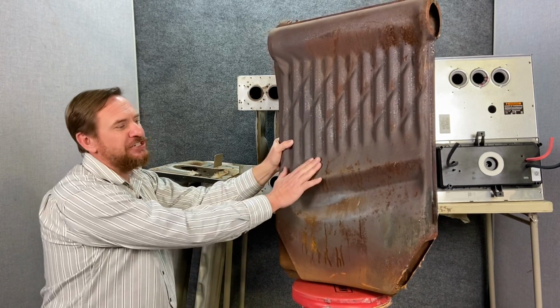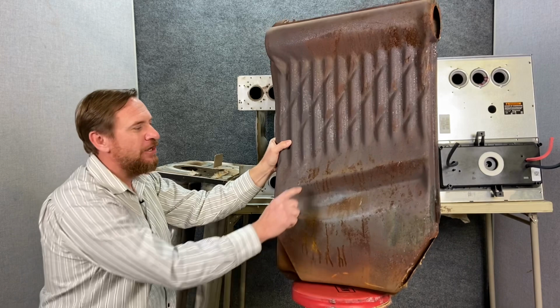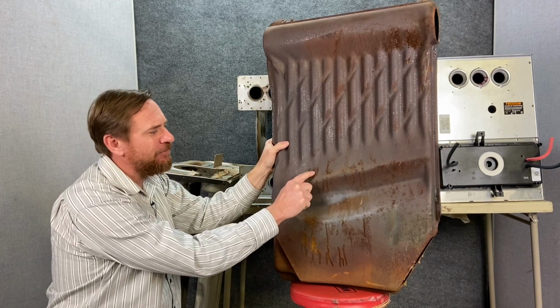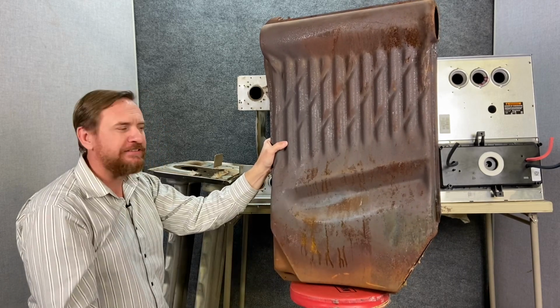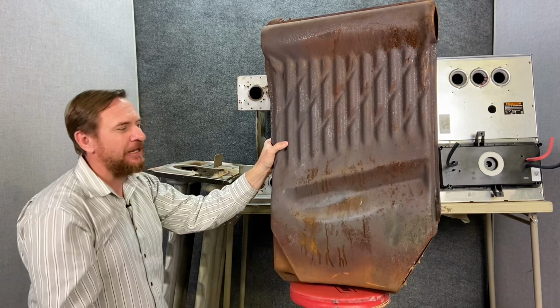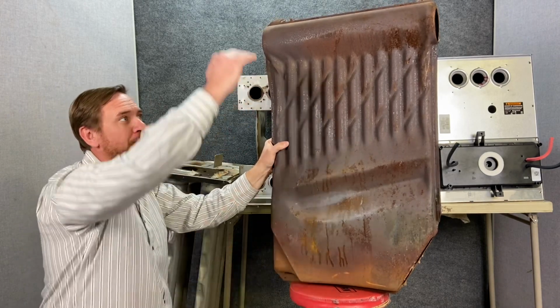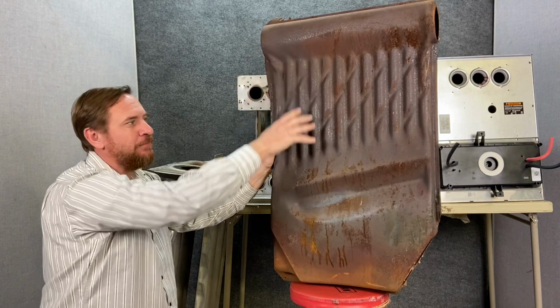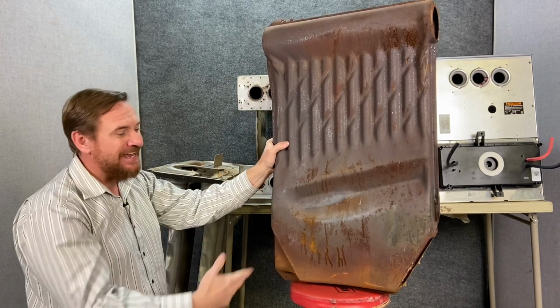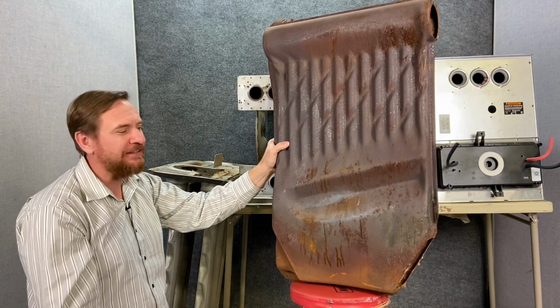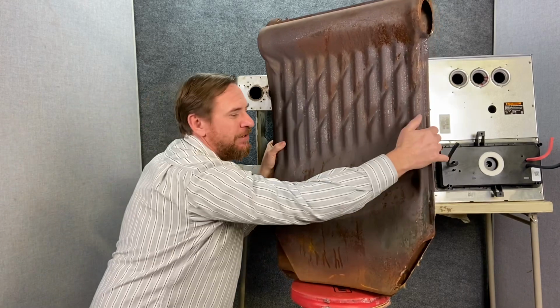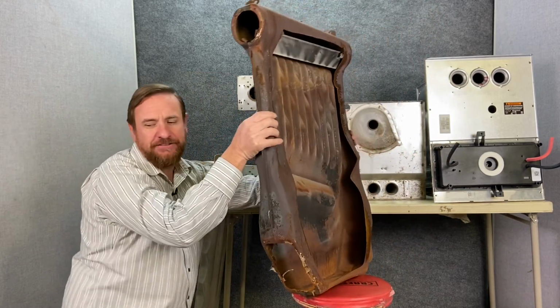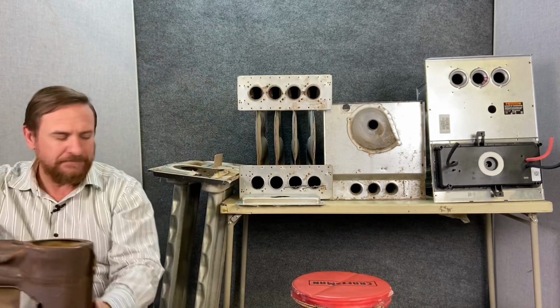So these old heat exchangers were notorious for leaking. We can see here some very heavy rust spots, and I'm sure if we were to do a water test, we'd find out that this heat exchanger was leaking. It's also very common for the evaporator coil that's set on top to leak moisture down on this, and they would rust out. They simply rust out over time. Nothing lasts forever. But this is one of the older styles, a natural draft furnace, natural draft heat exchanger.